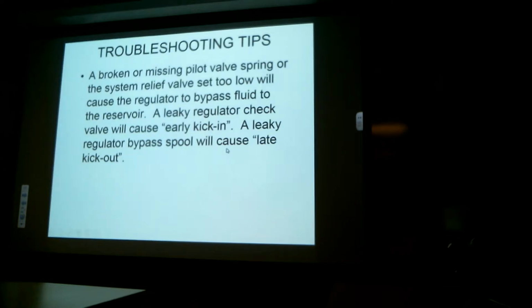Broken or missing pilot valve spring in an unloading valve. Well, to cut right to the chase, the unloading valve goes right to bypass. The spool, the pilot valve, and all of those in unloading valves will float to the upward position, which now triggers the unloading valve to bypass fluid back to the reservoir. There's no force to hold the pilot valve down, so the unloading valve responds by just dumping all of the system pressure through the bypass spool.